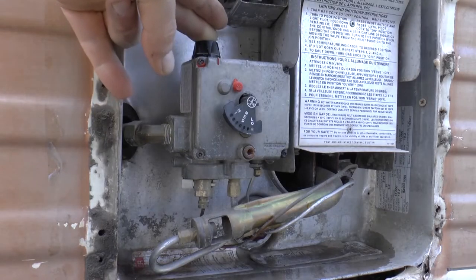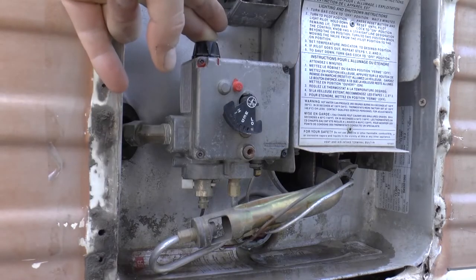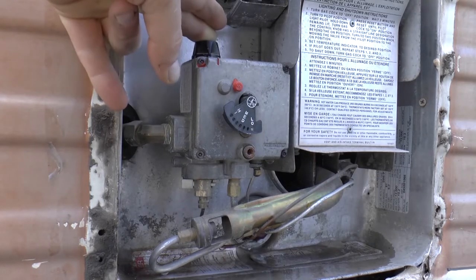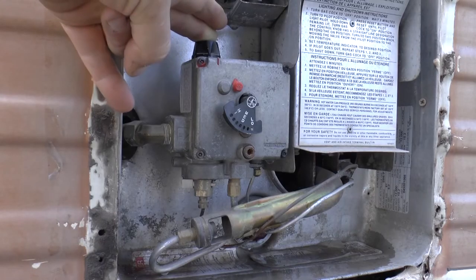Now that your pilot light's lit, you can hear it going and you can also verify that you see the blue flame. You're going to want to continue to hold this button down for about a minute and a half or so, until your pilot light warms up the thermocouple and then it's going to stay lit on its own. If you let go now it'll probably go out and you'll have to start over.